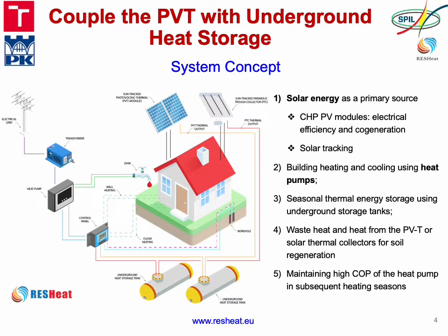The sun-tracked solar collectors produce high temperature heat, stored in an insulated underground heat storage tank and used for domestic hot water preparation. We also use waste heat from the sun-tracked solar collectors and PVT modules to regenerate the ground via borehole heat exchangers. The underground energy storage unit increases the heat pump COP, so less electrical energy is needed to power the heat pump compressor.